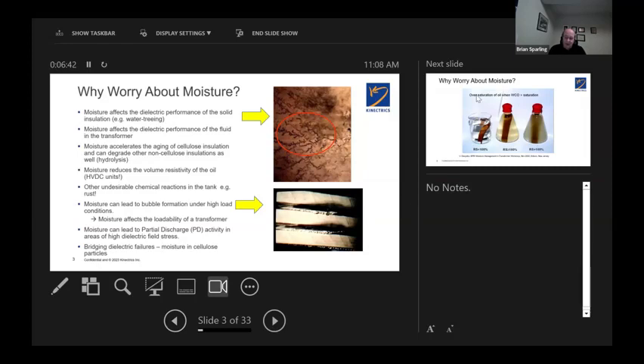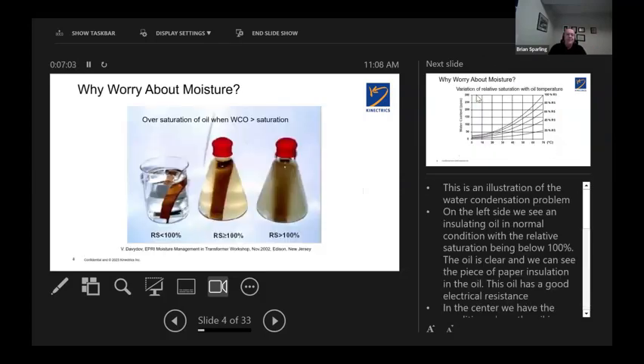So what's happened here is that you have reduced the dielectric capacity between turns of the winding, or in this case, between the sections, and the result is an immediate turn-to-turn dielectric failure. Boom, the transformer's life is over. This is what we want to avoid happening in the transformer.